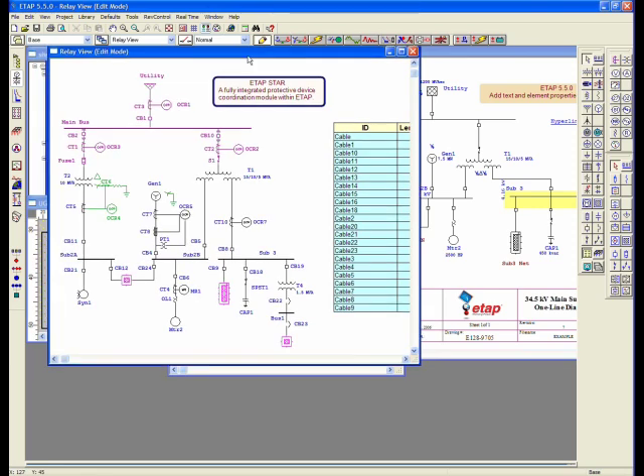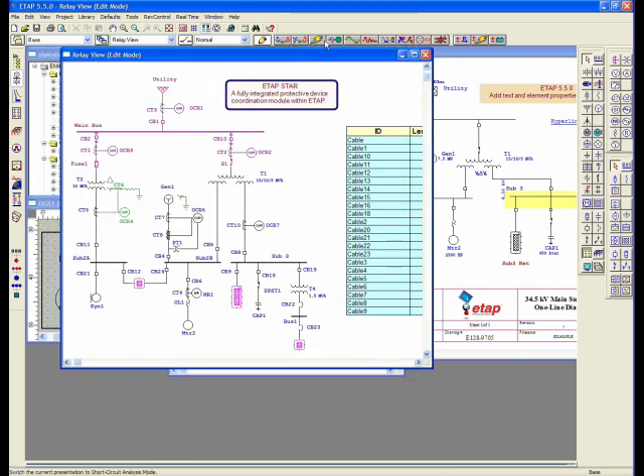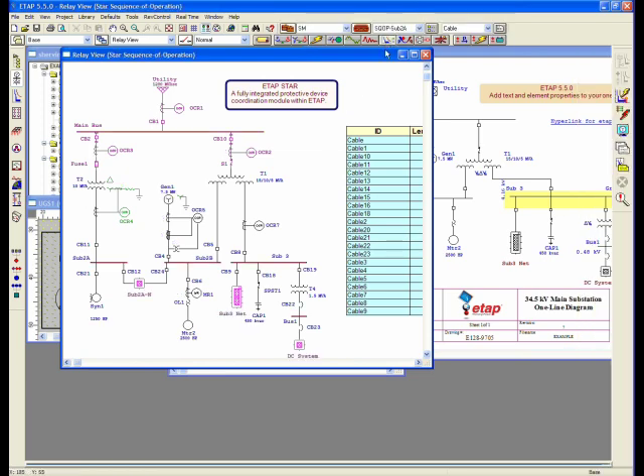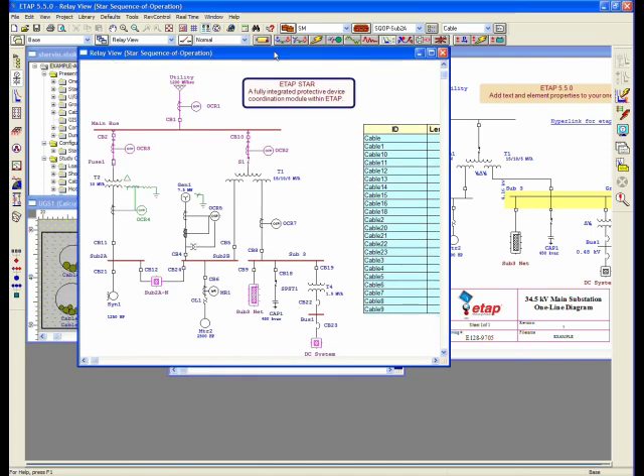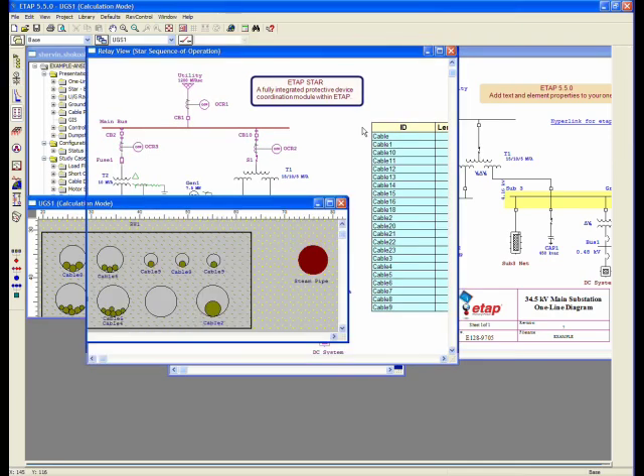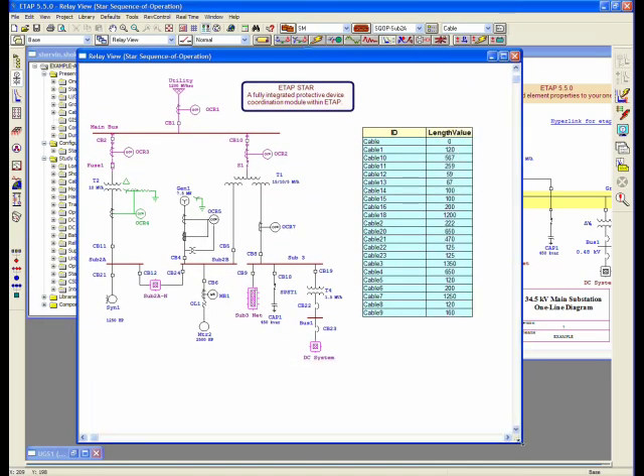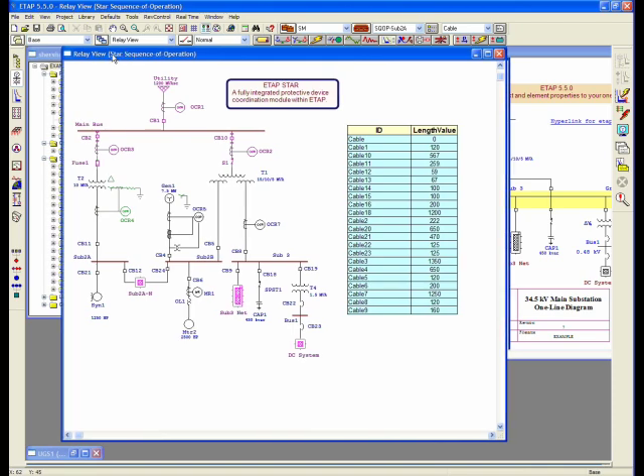The other modes within the program are load flow, short circuit, unbalanced load flow, short circuit motor starting, which we'll touch on briefly during this presentation. The mode we're most interested in is ETAP Star — a network analysis mode that provides tools to do device coordination studies. In the Star mode, you have tools for running short circuit, doing sequence of operation, getting reports, and viewing your time-current characteristic curves (TCCs).